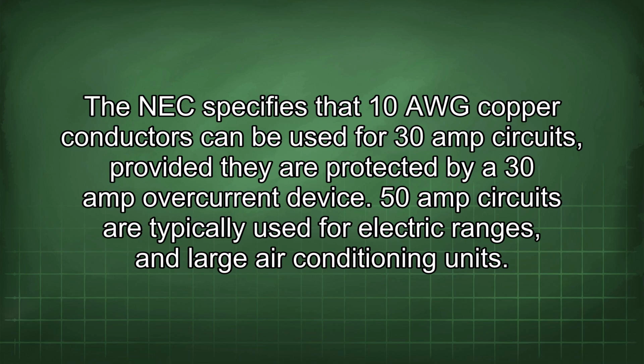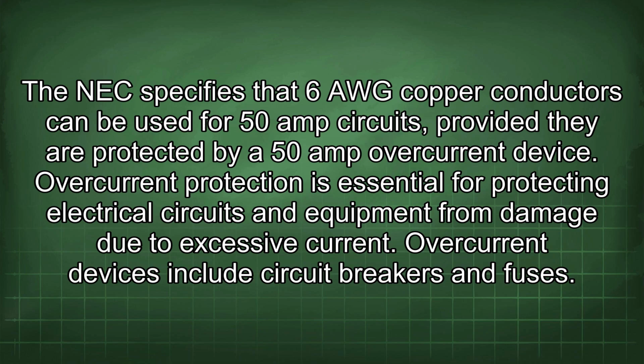The NEC specifies that 10 AWG copper conductors can be used for 30-amp circuits, provided they are protected by a 30-amp overcurrent device. 50-amp circuits are typically used for electric ranges and large air conditioning units. The NEC specifies that 6 AWG copper conductors can be used for 50-amp circuits, provided they are protected by a 50-amp overcurrent device. Overcurrent protection is essential for protecting electrical circuits and equipment from damage due to excessive current.